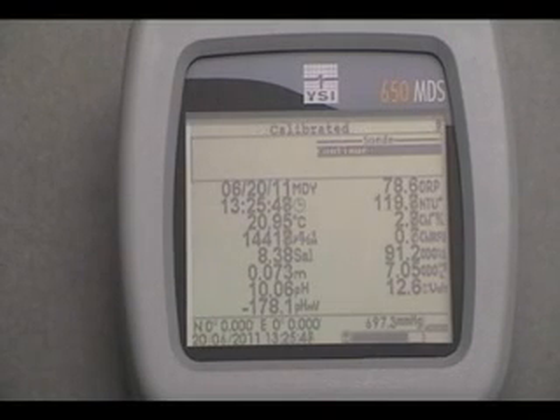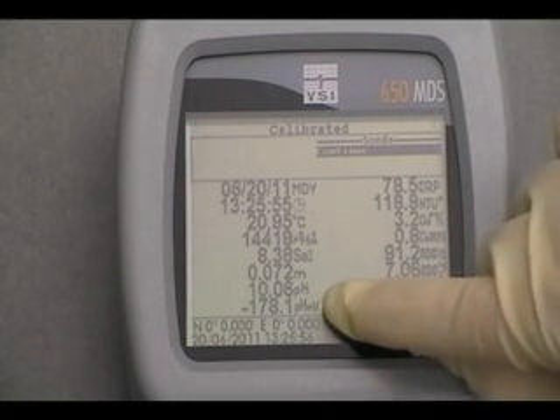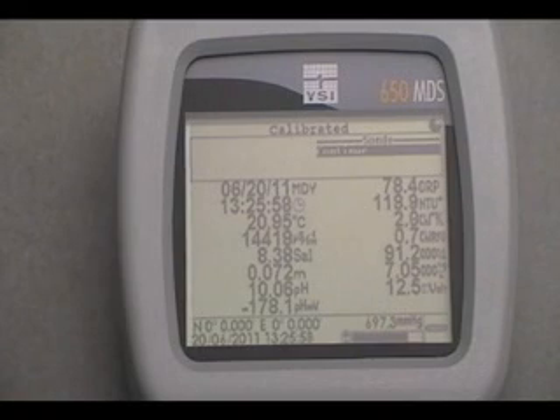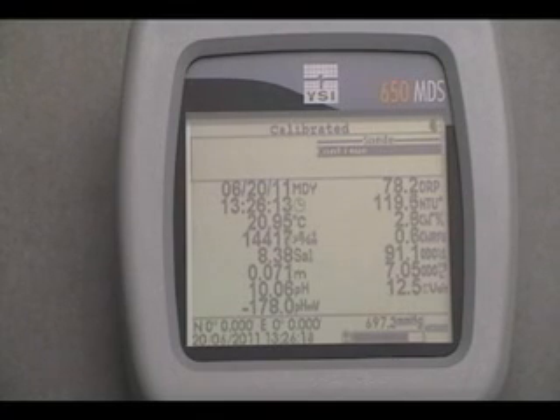Step 17. Record the post-calibration pH reading in pH units and the post-calibration pH millivolts on the calibration sheet. The pH millivolts value should be between 165 millivolts and 180 millivolts below the pH 7 millivolt reading. If the difference is less than 165 millivolts, the reference solution inside the pH probe is likely too old, and it's best not to deploy this probe. The lifespan of reference solution inside the pH sensor is only 1.5 to 2 years. Press Enter to continue.